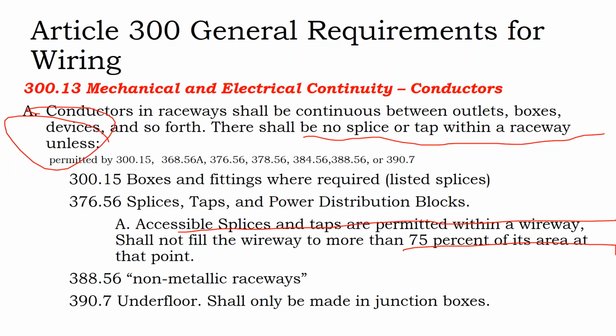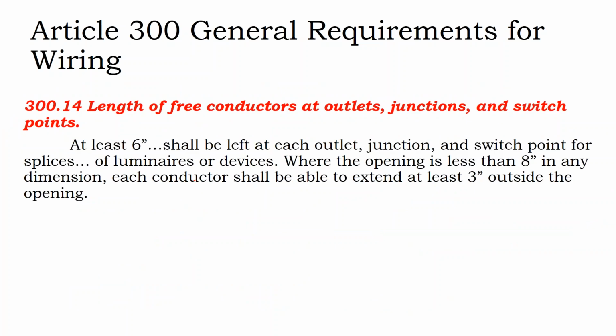It also has to be a fitting that's listed, and so again, you might find an outside of the box splice kit, but it's only listed for direct burial. It's not listed for all other environmental conditions. And so there are certain exceptions where you can do splicing outside of a box, but generally that's the exception to the rule, not the standard. When you're doing splices on a solar array, you really need to be putting it inside of a box. Those MC4 connectors are a housing for that splice connection. It's also listed for that purpose.